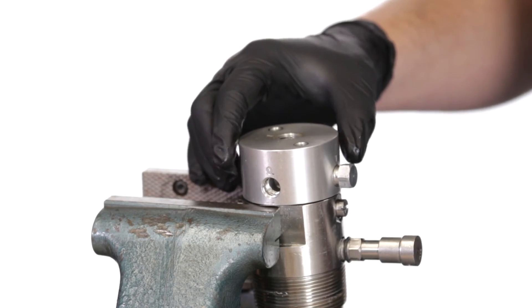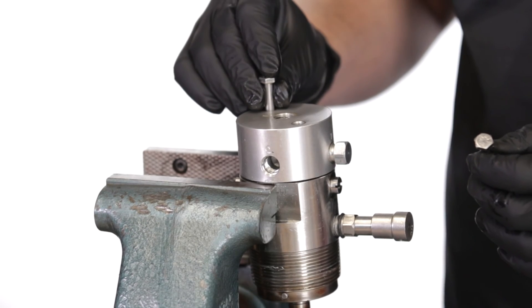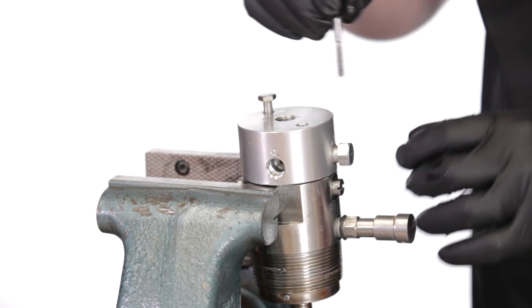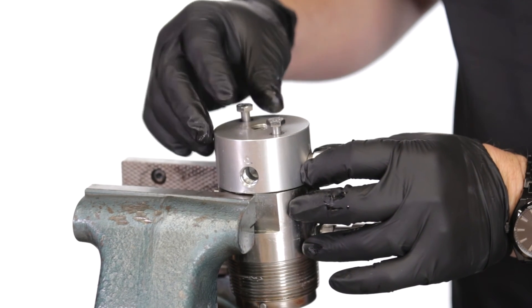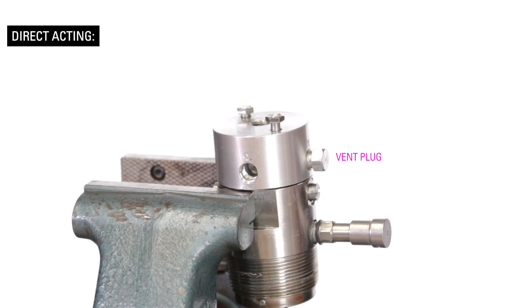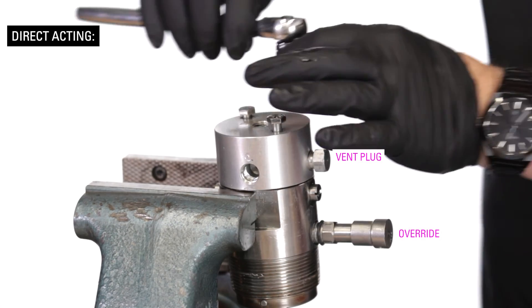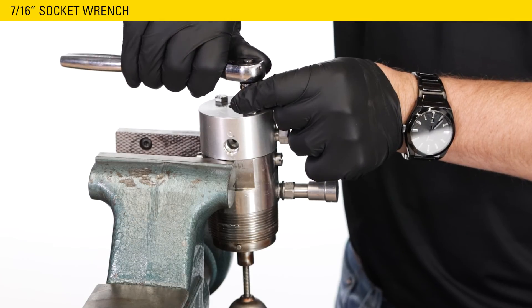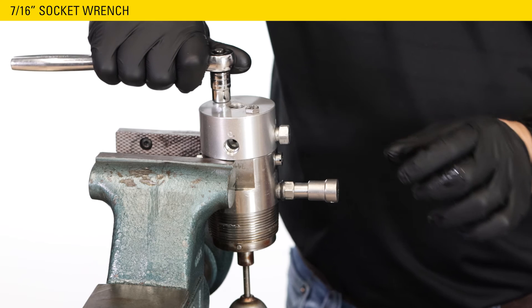Next, reattach the pilot housing to the body. This is where you will decide if you want direct acting or indirect acting. For direct acting, which is what we will be doing, align the vent plug on the same side as the override. Tighten the two bolts evenly with the 7-16th wrench.